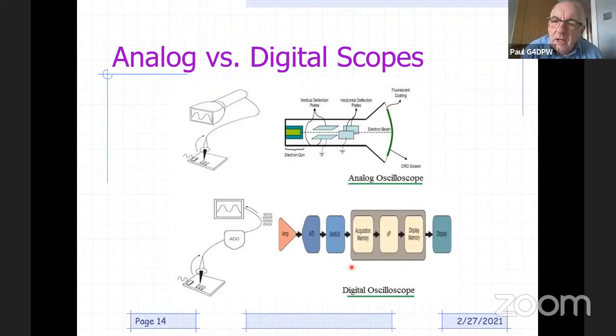One thing I would like to put forward as a suggestion, that is that when you, for instance, want to look at a signal, let's say you're getting close to the edge of the bandwidth. If you put in a signal, say, let's start at 50 kilohertz as an example, and you fill up the full screen, you're taking up all 10 divisions. But when you get to the actual bandwidth frequency of 100 megs, the signal will reduce down to approximately 7.2 divisions. Right. And I think that's something people need to be aware of.